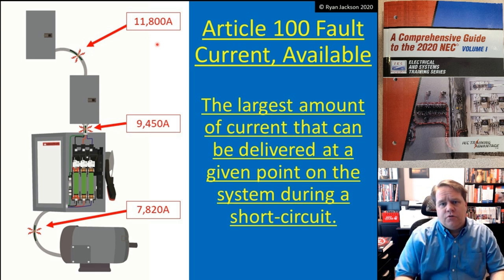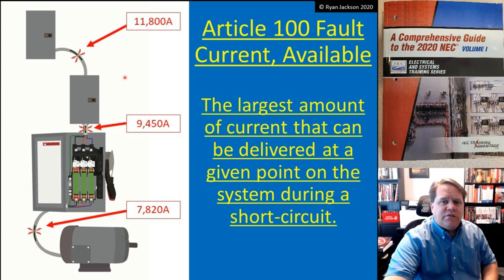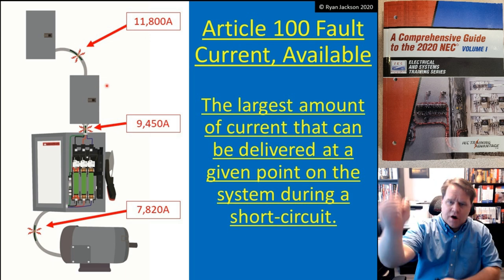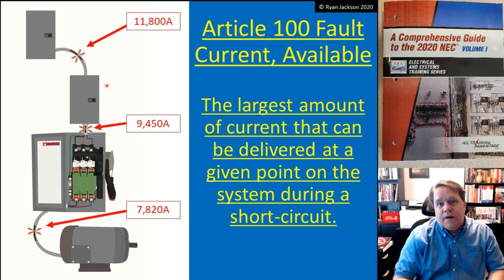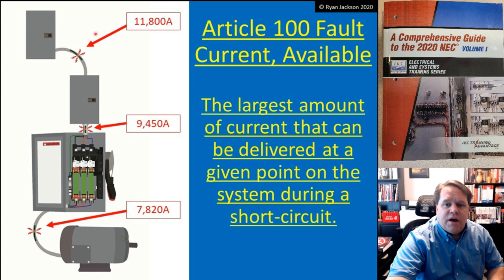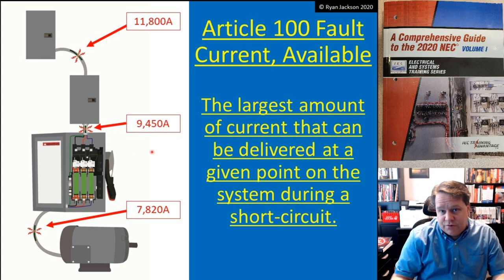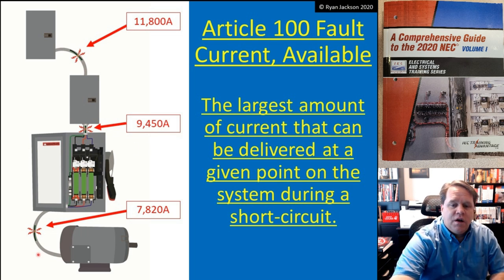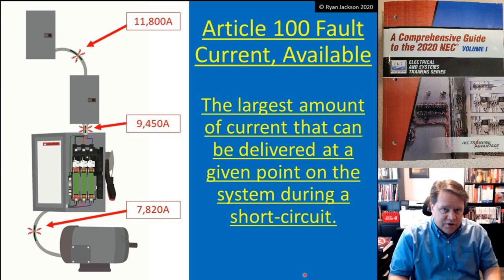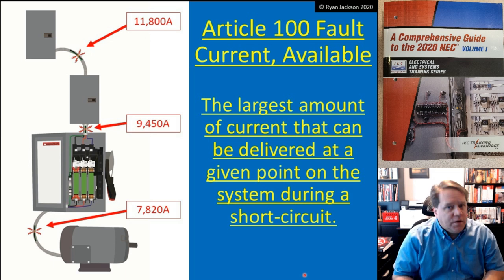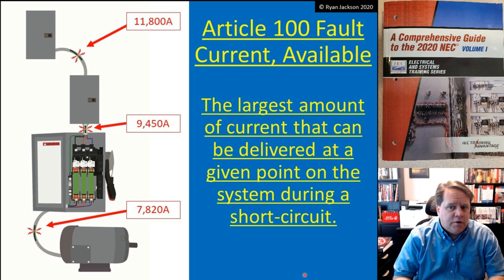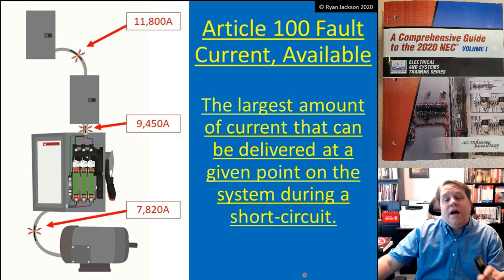How much current would flow at a given location is going to be a function of that location. In this conduit here, if I were to take a saw and cut through it, how much current would flow during that fault? At that point on the wiring system, we're going to say 11,800 amps. As I go a little farther away from the source, maybe it's 9,450 amps. And then as I get even farther from the source, that number goes down to maybe 7,800 amps. The available fault current is different at all points of the wiring system, and it's absolutely imperative that I know what it is. At a minimum, we know we have to mark it on some equipment.